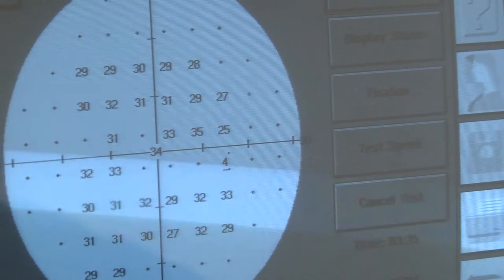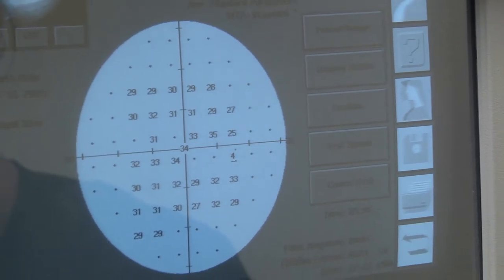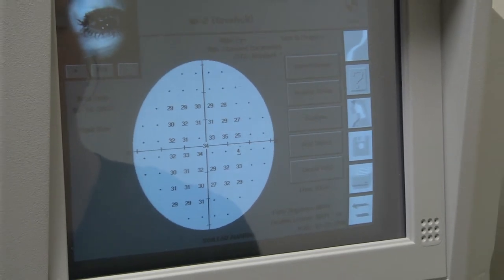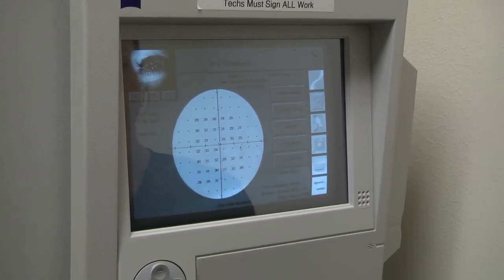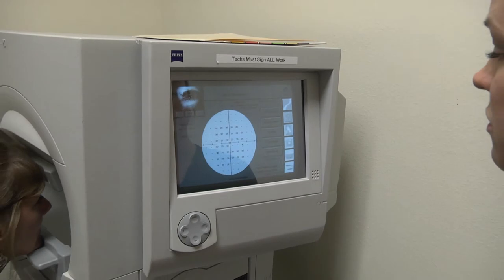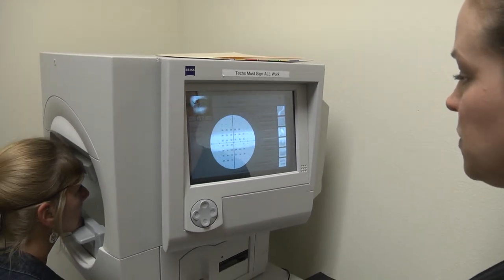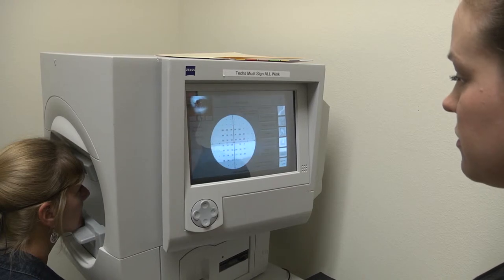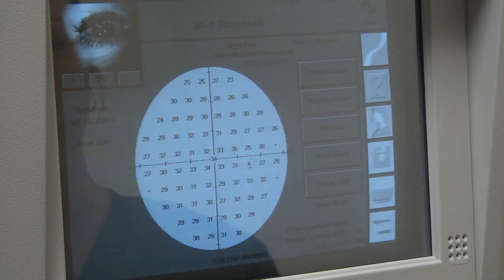Go ahead and press OK and tell the patient the test has begun. While the patient is taking the test, you'll notice that the dots on the screen turn into numbers. You want to watch for any movement of the eye, excessive blinking, or patients can sometimes fall asleep during this test. Just be a cheerleader for them — let them know they're doing well. Continue to monitor the screen, as this encourages the patient to do the test as best as they can. Once the test is over, a screen will pop up saying the test is finished and asking if you would like to save the test.